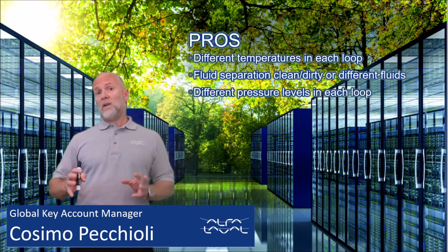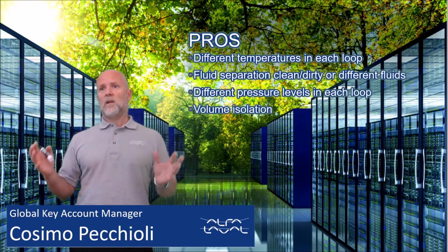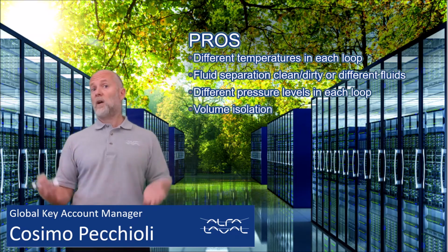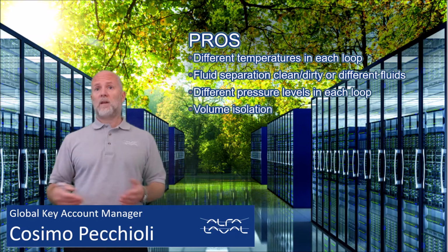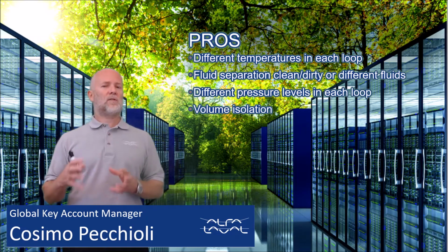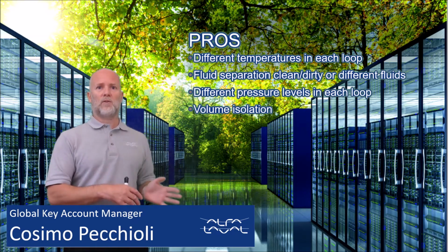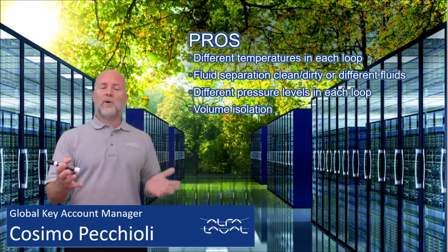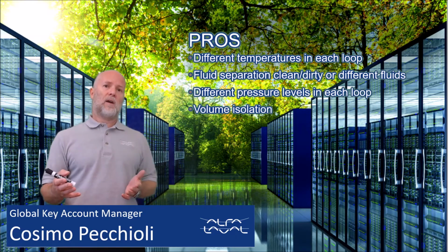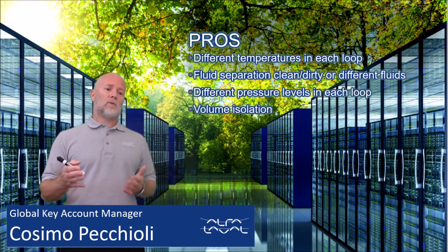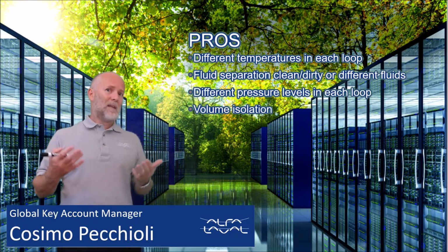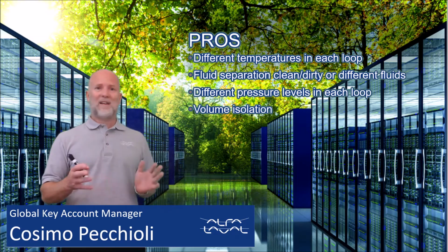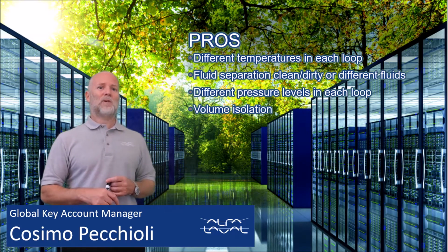If you have a large facility, you have a large amount of water moving around with very large pipes, and you might not want to have these very large pipes inside of your server room for a safety consideration, of course. Think about if you are in a seismic area and you have a tremor, all those joints might leak at a certain point, and if you have a 24-inch pipe inside of your server room, it's a situation maybe you don't want to experience.